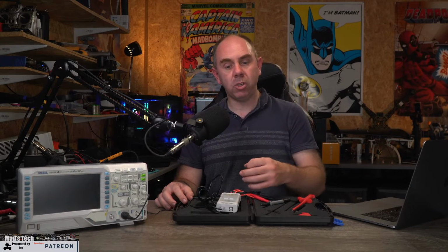Switchmode power supplies specifically can have some extremely high DC voltages as well as AC input as well. The reason for having the differential probe is to add an additional layer of safety. However, that does not mean you can just go prodding about and nothing bad will happen. You do still need to be very careful at what you're doing. And as I've already mentioned, you really do need to be using a mains isolation transformer as well.